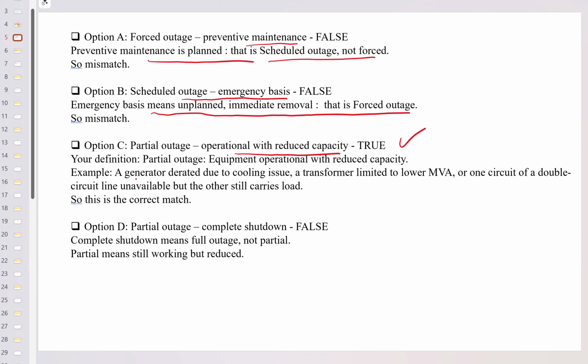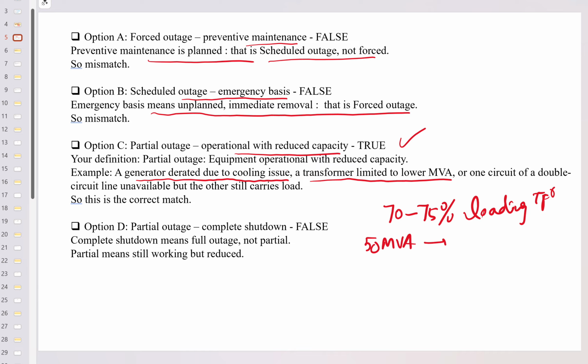For example, due to a cooling issue, a transformer is limited to lower MVA. We already saw that 70 to 75% loading is preferable for a transformer. Suppose there is a 50 MVA transformer, so you do not go to 70% times 50 MVA, that is required to protect it from thermal damage.